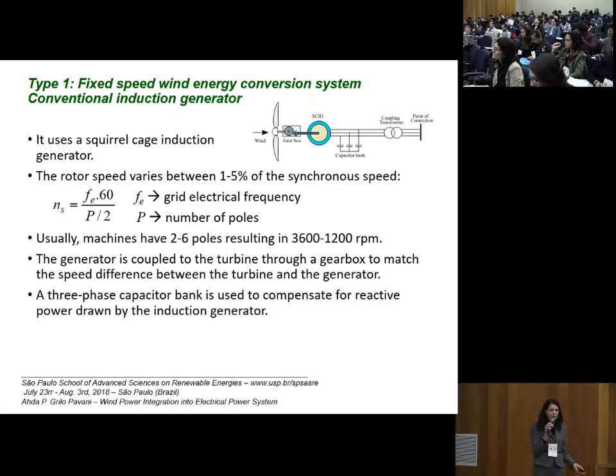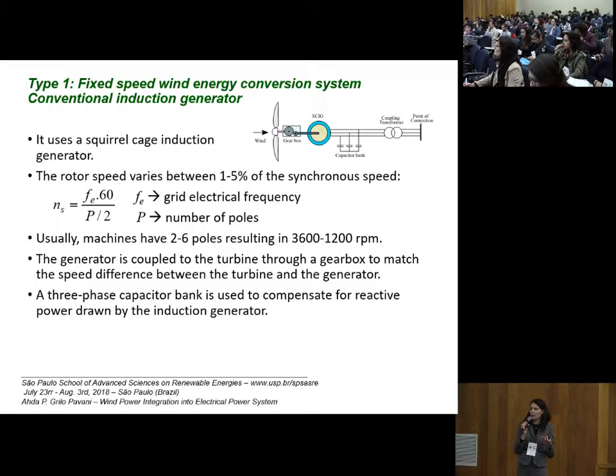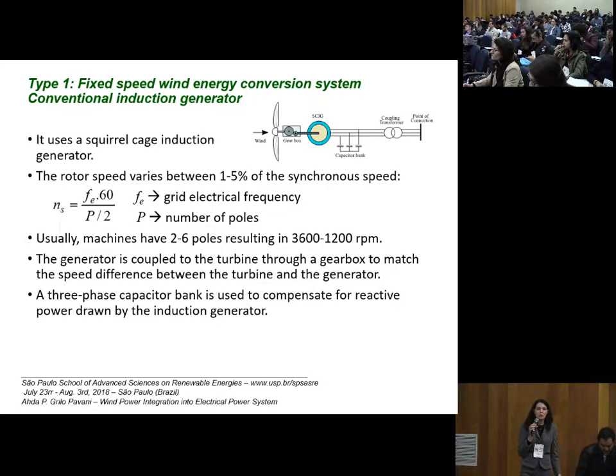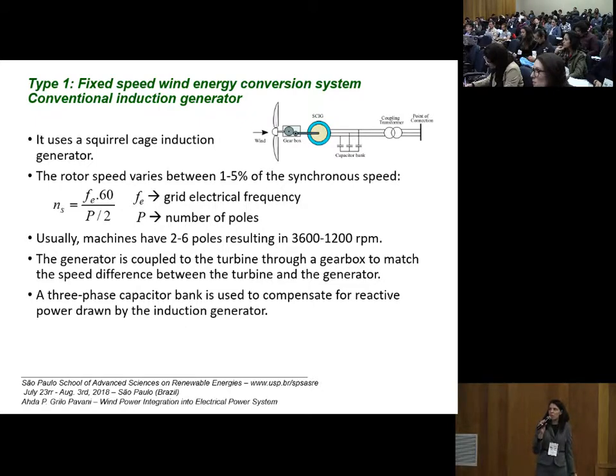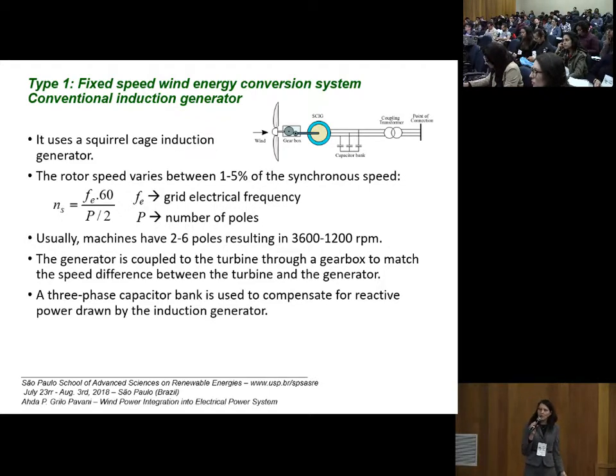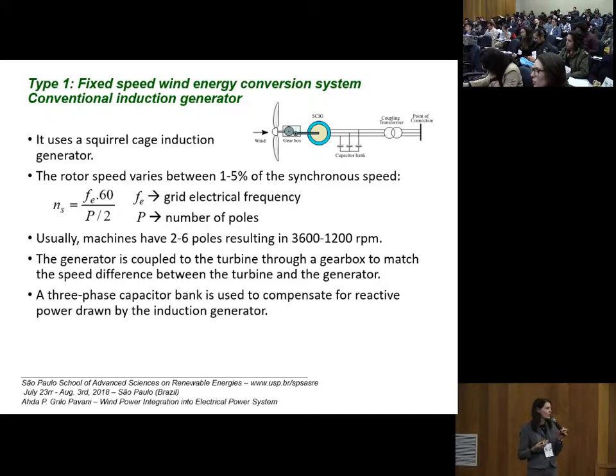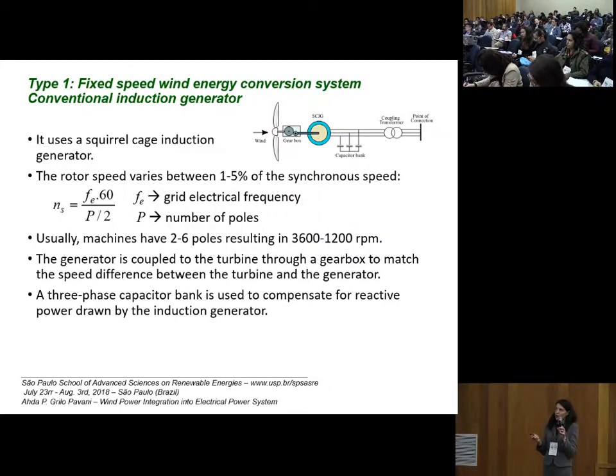Usually, the squirrel cage induction machines have 2 to 6 poles, resulting in a rotary speed of 3600 to 1200 RPM. We have to couple the generator to the wind turbine through a gearbox to match the speed difference between the turbine and the generator. Also, because the induction generator consumes reactive power from the grid, a capacitor bank is connected at the output of the wind generator to improve the power factor.